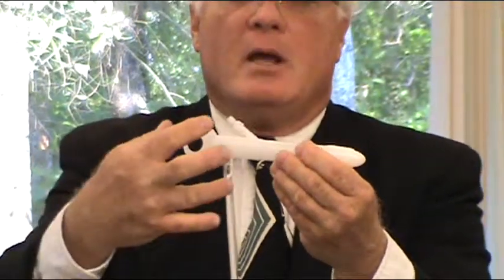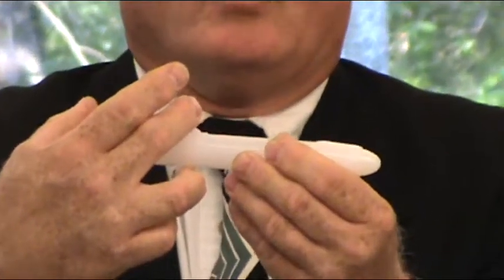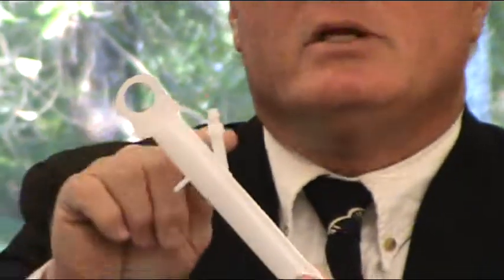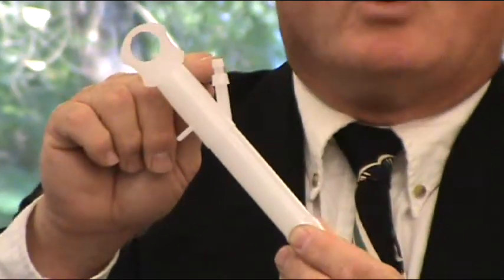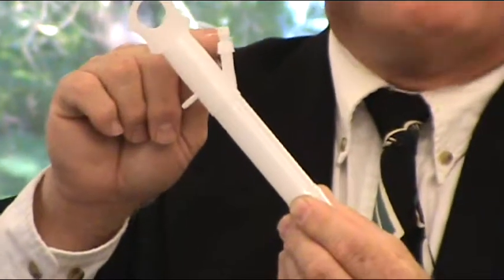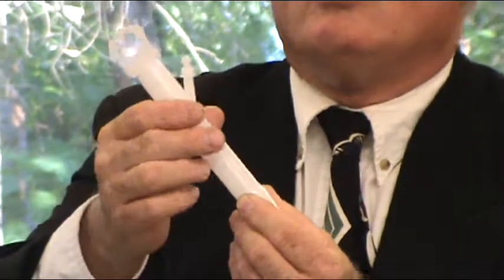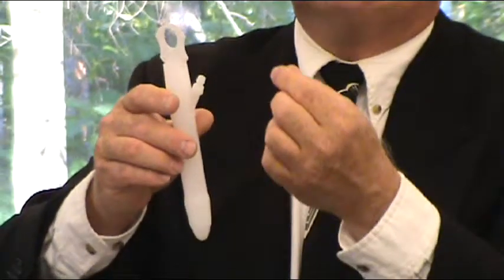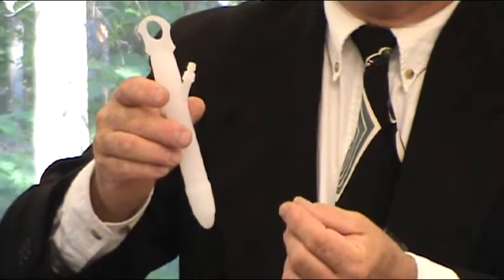Underneath is a finger tab, because during the insertion you place your finger on the tab on the bottom and on the inlet port. Our inlet port is also part of our design patent, and this incorporates a 3/8 and a 1/4 inch. Commonly on all class 2 colonic irrigators, the 1/4 inch inflow is used. On a gravity flow system, it is found best to use the 3/8. Our holes that go through the port are increased size to allow the maximum flow of water for both a gravity flow and for a class 2.